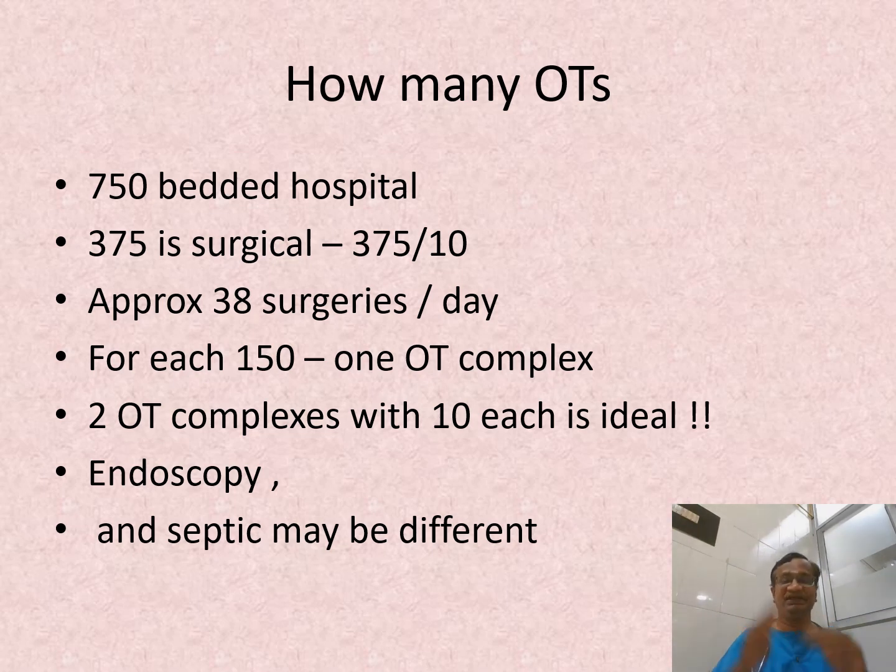So approximately you divide by 10. That is 37.5, 38 surgeries per day. For each 150, one OT complex. 2 OT complex with 10 each is ideal.